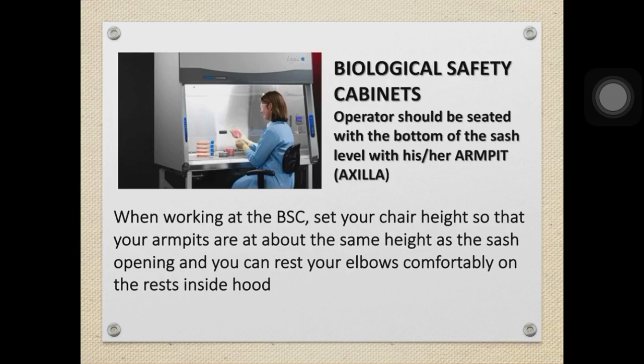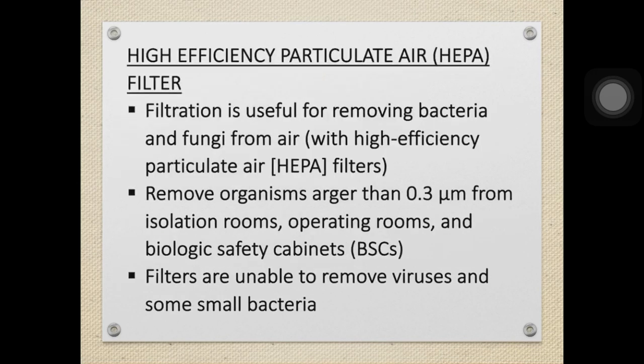When working at the BSC, set your chair height so that your armpits are about the same height as the sash opening, and you can rest your elbow comfortably on the rest inside the hood. High efficiency particulate air filter, yung mga biological safety cabinet po may HEPA filter. It removes organism larger than 0.3 micrometer in diameter. Sino po ito? Yung mga bacteria, yung mga fungi, pero hindi po yung mga viruses. Yung mga viruses, because of their small size, can pass through this filter.